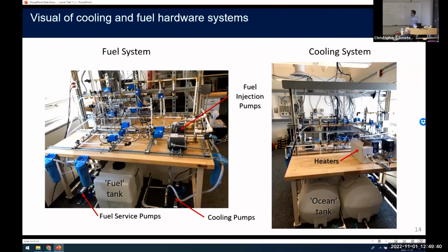And then this is just a visual of the fuel and cooling system. On the right, you can see the cooling system. We have 2 65-gallon tanks on the ground. The left tank we call the ocean tank. The pumps pull from this tank and run through those 2 parallel paths we talked about, and across these 2 heaters in the boxes. The variable frequency drives on the table provide the waste heat to the heaters, and then the flow goes back into the tank on the right, which is the waste heat tank. So then we can see the temperature rise across the system.